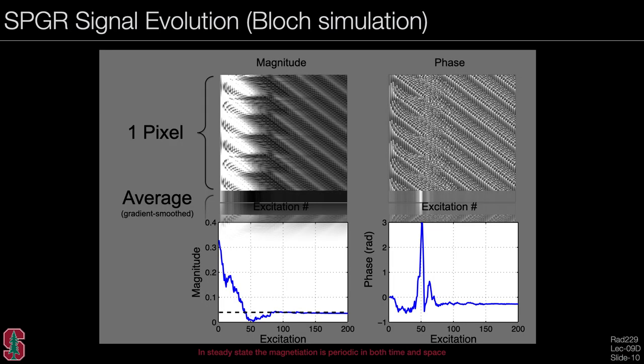Viewing the signal evolution across a pixel, the bottom shows the average magnitude and net phase of the signal from the voxel. While the approach looks extremely complicated as steady state evolves, in the steady state the magnetization becomes periodic over time and also periodic over space. This profile is shifting through the voxel.